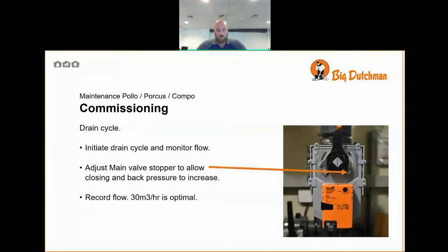And for the drain cycle, the main pressure line will try to close to create a back pressure on the drain line. So we initiate the drain cycle and monitor the flow. We adjust the stopper on the Belimo valve when we record a flow of around 30 cubic meters per hour. So we allow the valve to close just far enough that it's producing enough backflow, and then we lock it off.